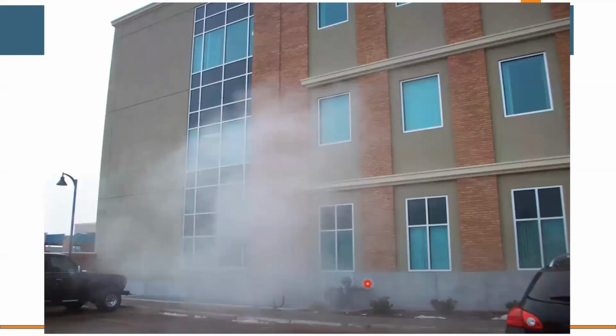You're seeing a lot of architects too not give adequate room for mechanical venting or vent runs that might get the products of combustion out the top of the building. So we're seeing a lot of sidewall vent applications. In this case, it's below the sidewalk, and you can see the plume that the boilers give off during high fire. Okay, this has a lot of potential repercussions. It also makes these windows not real usable. There's challenges here.